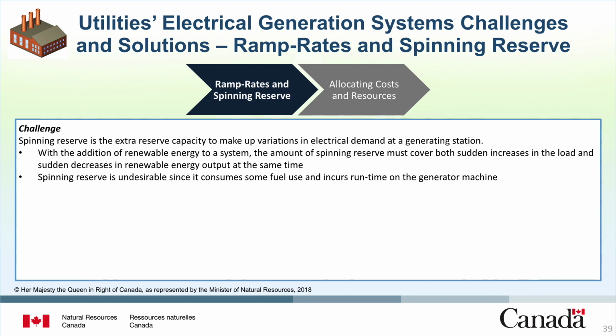Sites installing large renewable systems, especially on small utility grids, should realize that a kilowatt delivered does not generally equal a kilowatt saved at the generation plant. It takes time to start a generator and increase its power output, especially a coal or nuclear plant. The heat engine portion of a generator is always operated with some extra reserve capacity to make up variations in the electrical demand. This operational override is called spinning reserve. Without renewable energy generation, the amount of spinning reserve must cover anticipated changes in the load, but with the addition of renewable energy to a system, the amount of spinning reserve must cover both sudden increases in the load and sudden decreases in renewable energy output at the same time.